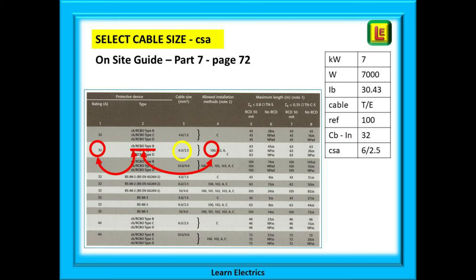Now turn to page 72 to select the correct cable size. There are two entries for 32 amp breakers, but looking at the fourth column there is only one that matches up with reference method 100, so choose the second entry. Check the details: 32 amp circuit breaker type B, reference method 100 — all shown in red here.